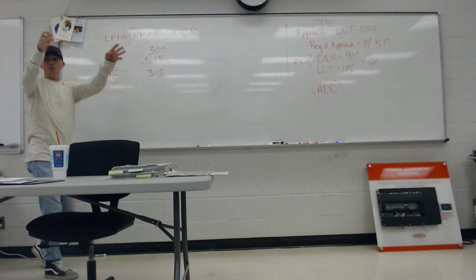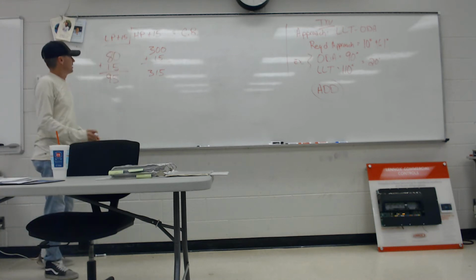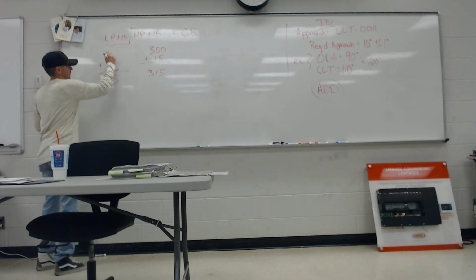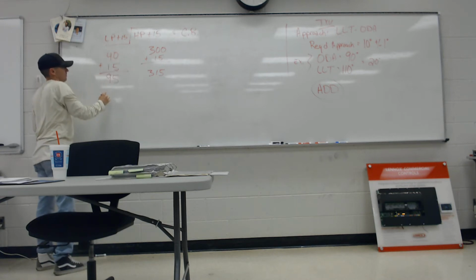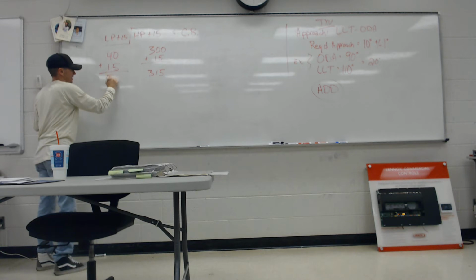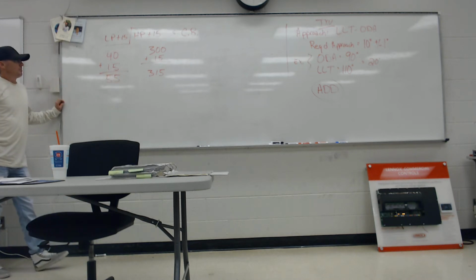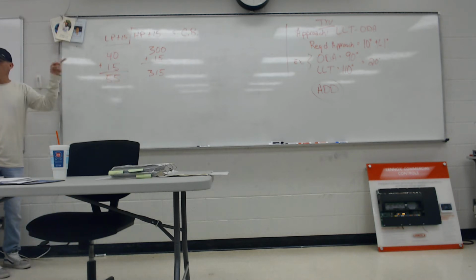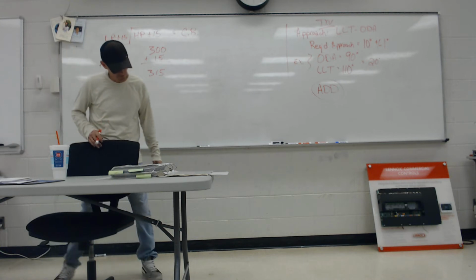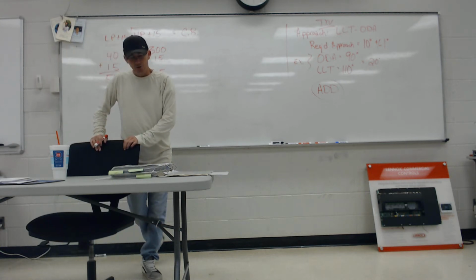You guys see, if we go from 72 in here with this number, but then take that same unit and put it in a walk-in cooler, now my suction pressure is hanging out at like 40 PSI. Add 15 to it, I got 55. My compression ratio just went from 3-to-1 to nearly 6-to-1. It doubled my compression ratio going from a 70-degree box to a 40-degree box. Good? Compression ratio, game over.